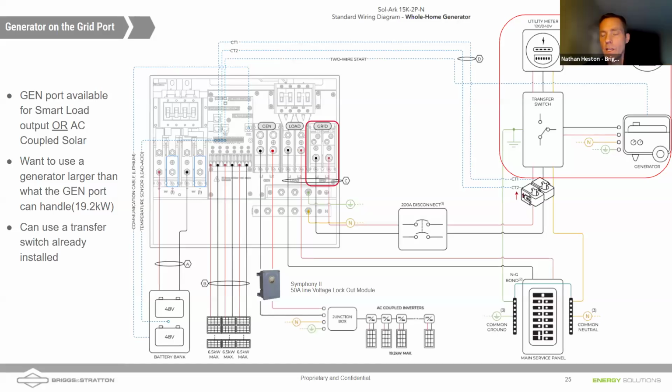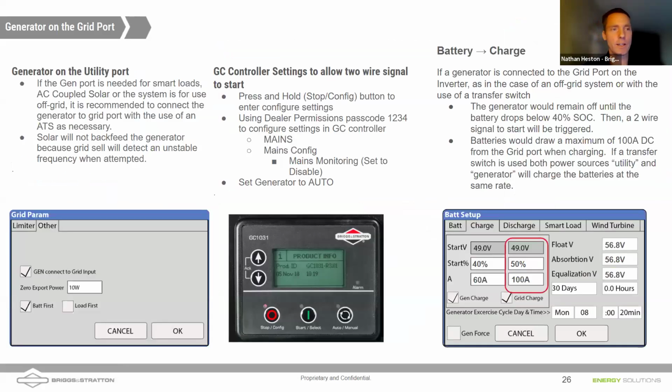Yeah, that's what I was thinking too. This is right out of the Sol-Ark manual, and I don't want to make excuses here, but it should be right after the meter at the first point of disconnect, which I believe should put that neutral ground bond inside the transfer switch. And Andy's saying yes. Oh, great. Good. So good, Daniel. Thanks, or Andy, thanks for catching that here with us.